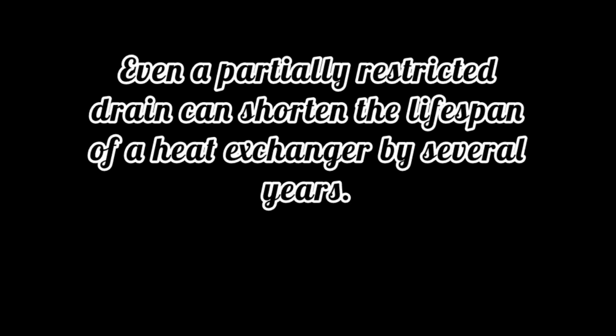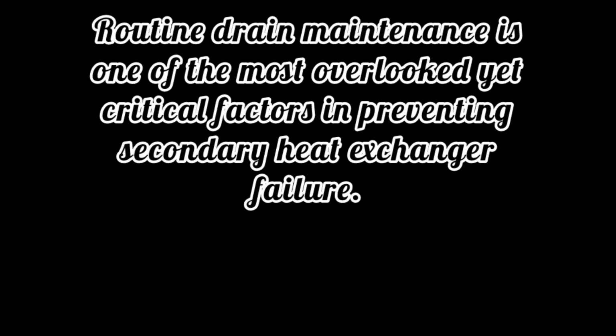Step 4. Poor drainage accelerates rust. Condensation must drain properly out of the furnace. When drain systems become clogged, misaligned, frozen, or improperly installed, water pools inside the secondary heat exchanger. Standing acidic water dramatically increases corrosion speed. Even a partially restricted drain can shorten the lifespan of a heat exchanger by several years. Routine drain maintenance is one of the most overlooked yet critical factors in preventing secondary heat exchanger failure.